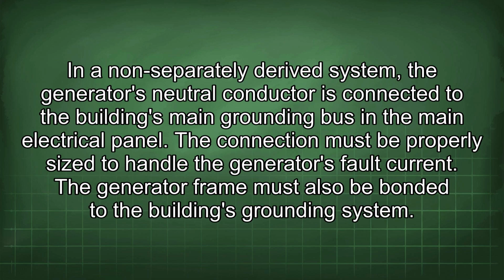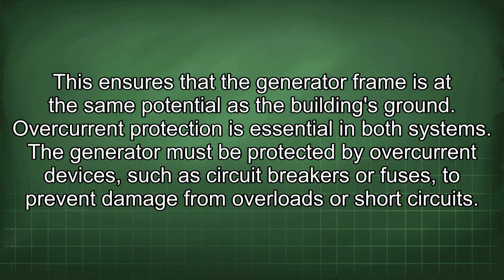In a non-separately derived system, the generator's neutral conductor is connected to the building's main grounding bus in the main electrical panel. The connection must be properly sized to handle the generator's fault current. The generator frame must also be bonded to the building's grounding system. This ensures that the generator frame is at the same potential as the building's ground.